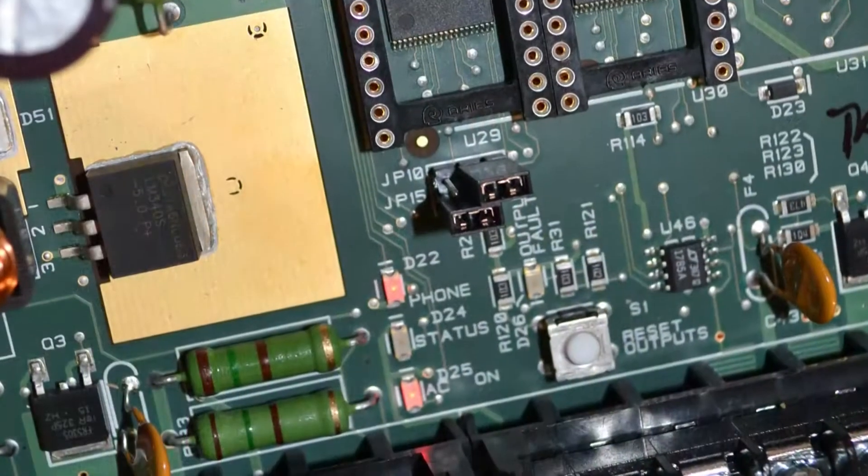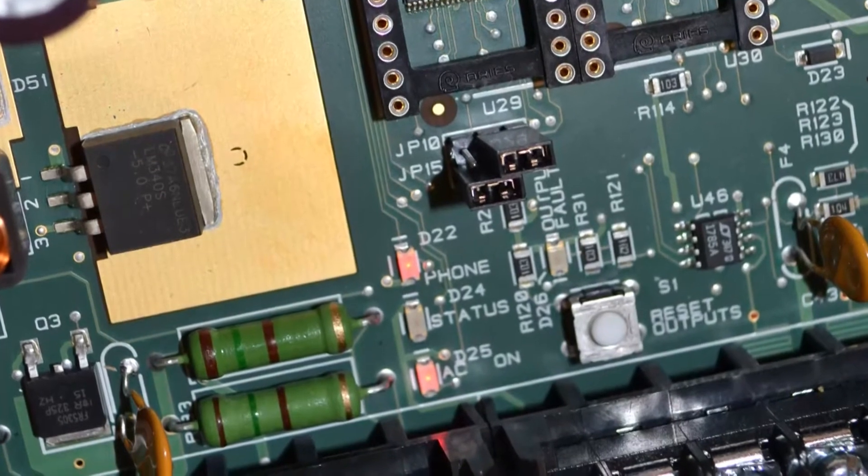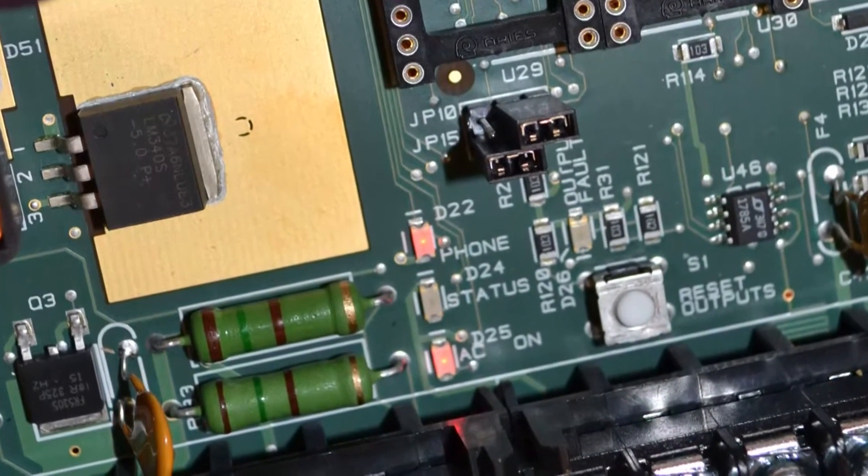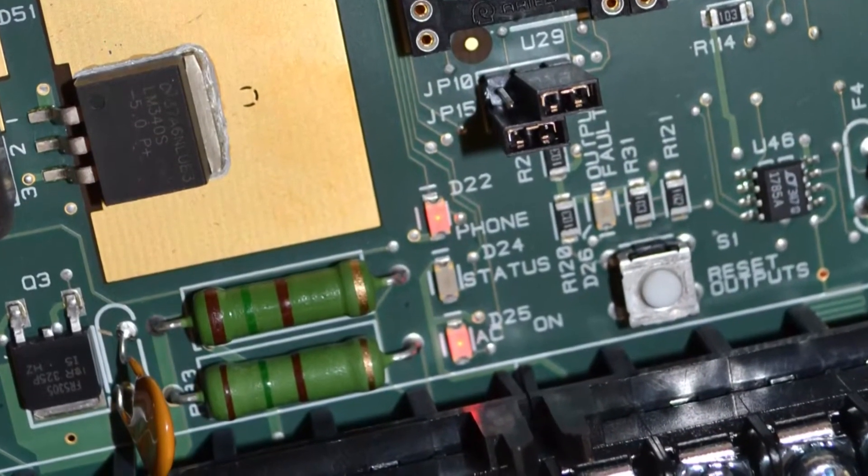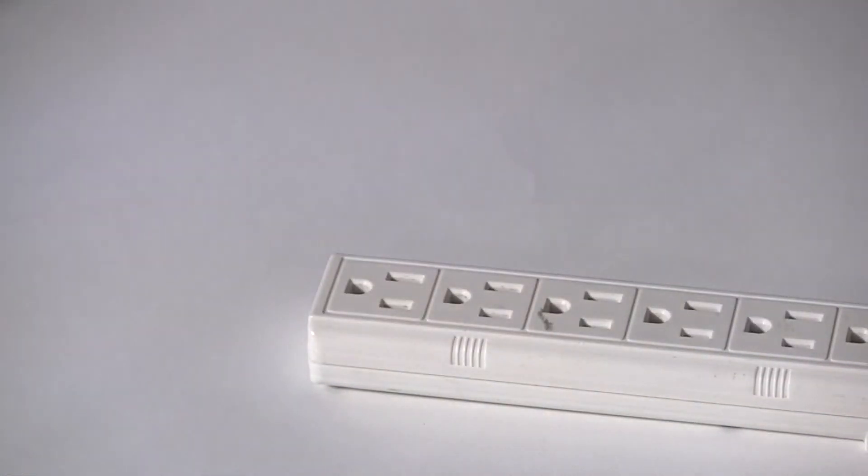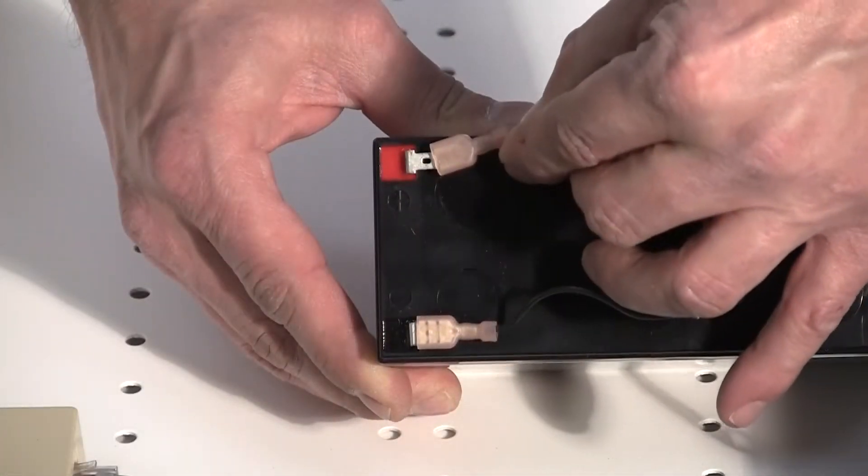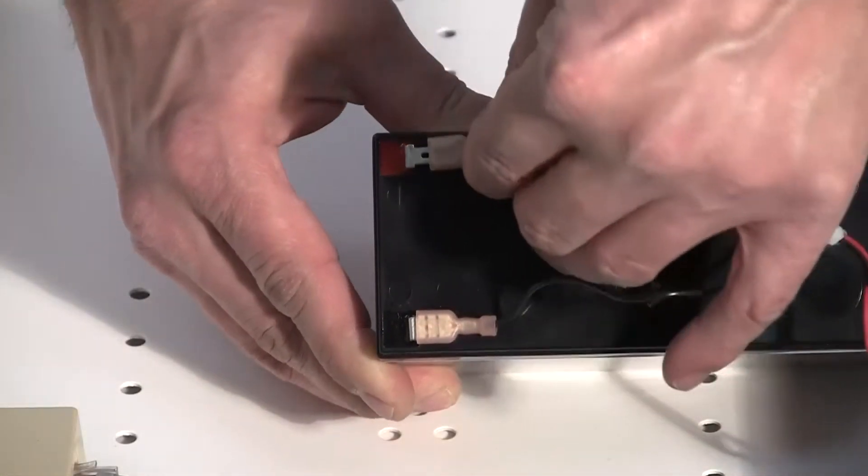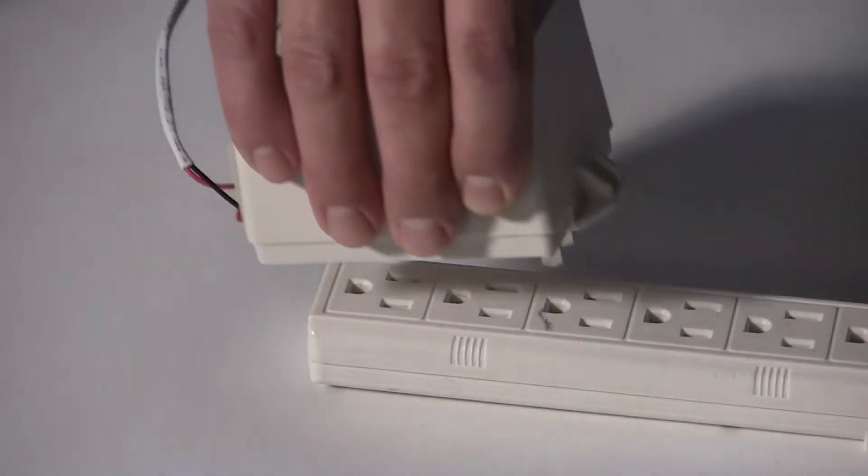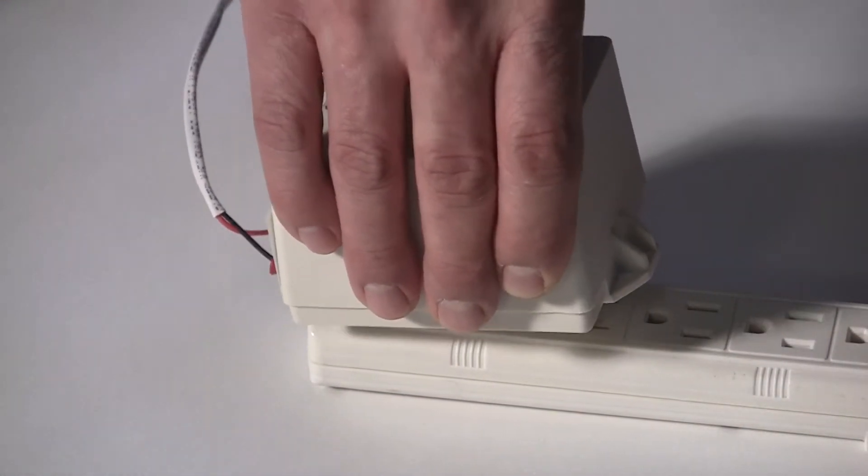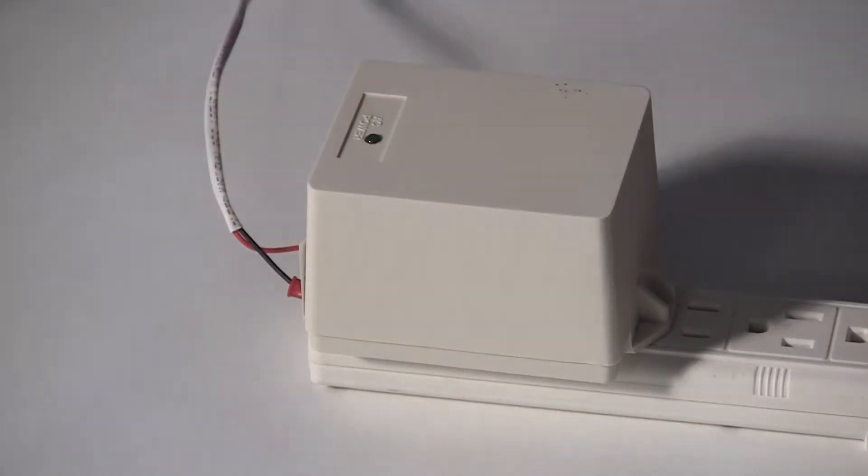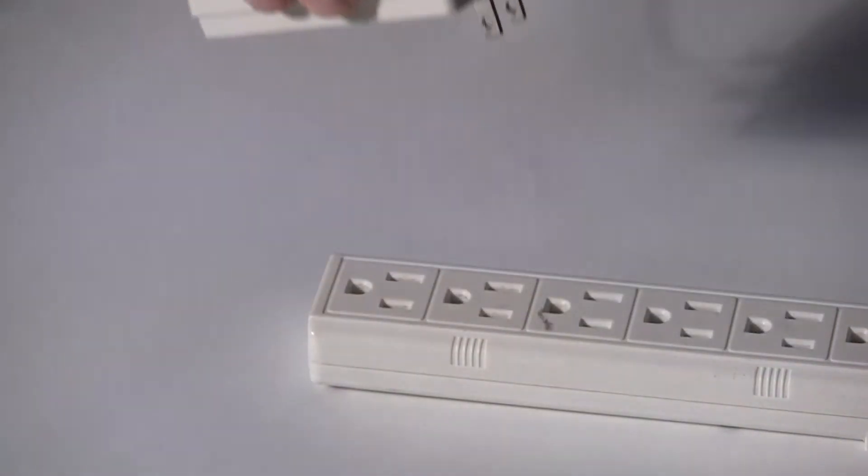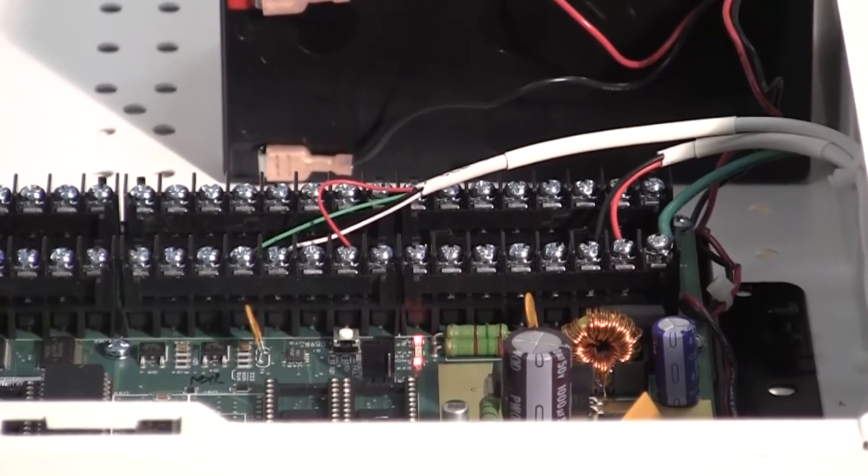The phone LED should be off unless the main incoming line is not connected or a house phone is in service. Now unplug the transformer. Connect the red battery lead to the 12VDC battery and plug the transformer back in. Allow the system to run for 10 to 20 seconds and then unplug the transformer again.